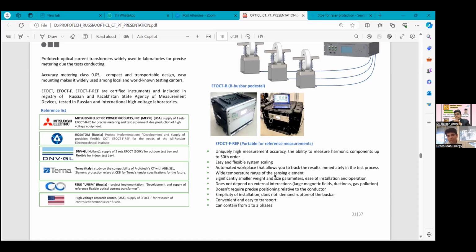Wide temperature range of the sensing element, significantly smaller weight and size, ease of installation and operation, and it does not depend on external influences: large magnetic field, dustiness, gas pollution. It doesn't require precise position relative to the conductor. Simplicity of installation, it does not demand rupture of the bus bar. Convenient and easy to transport. Can contain from 1 to 3 phases.